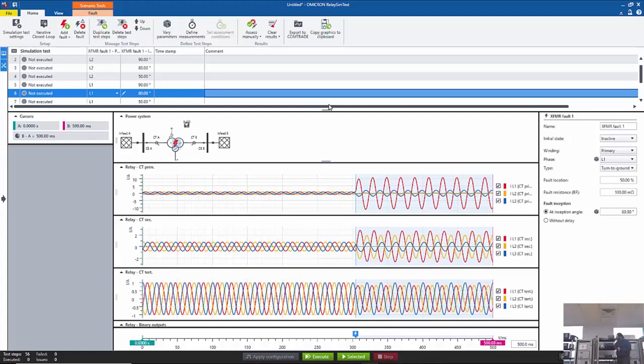I use the 430 for the additional three currents to test the tertiary side, and I use the CMC 356 to connect to the primary and secondary side. I got the feedback into the CMC 356 with only one general trip instead of using primary, tertiary, and secondary trips. This is all about the power system.